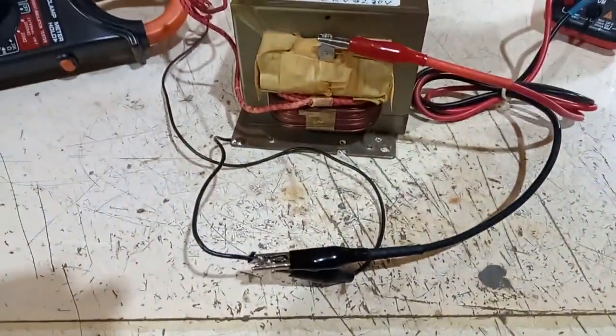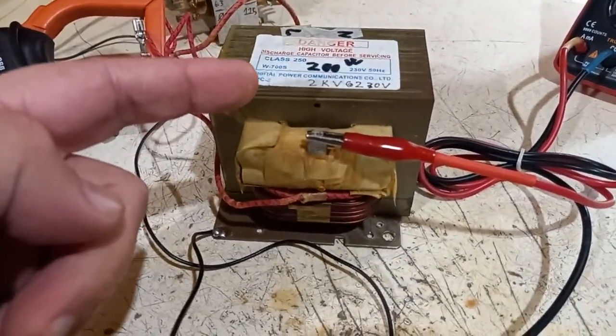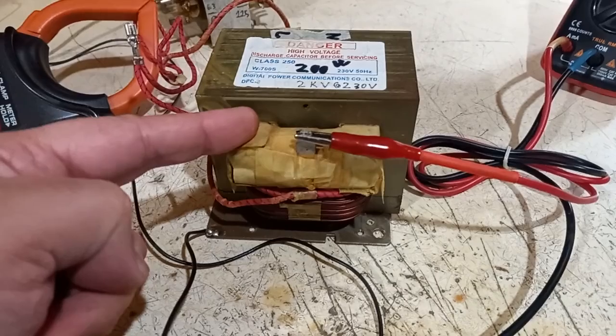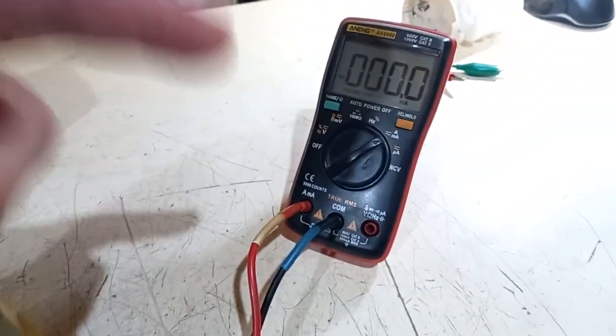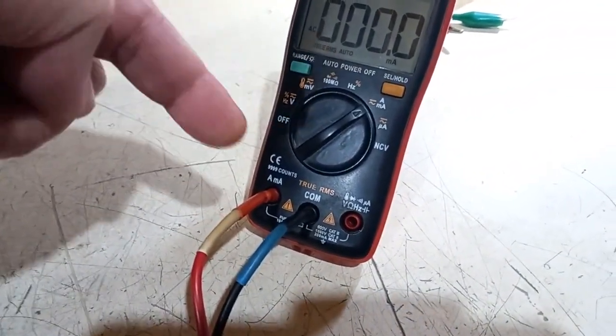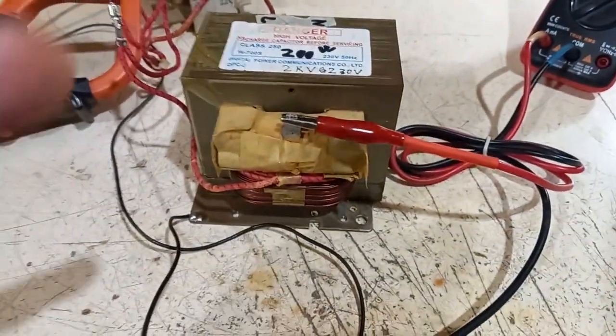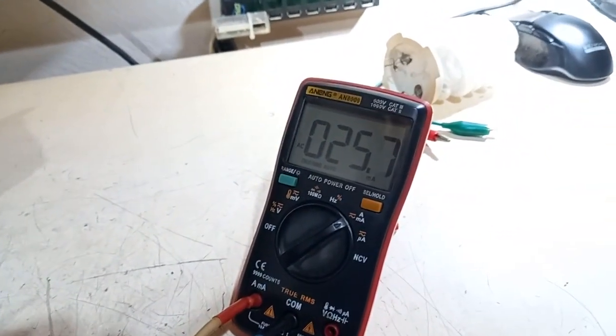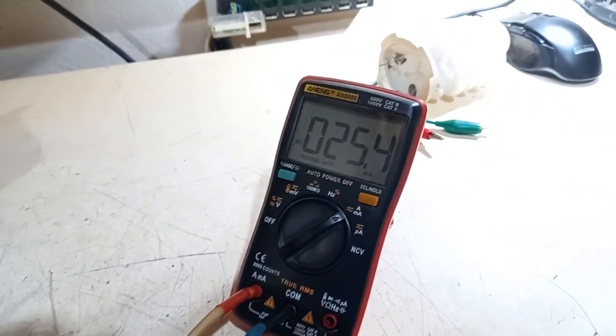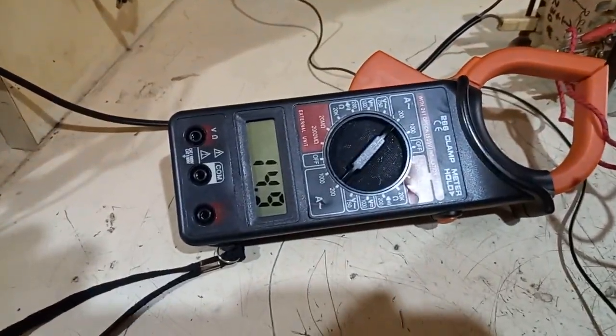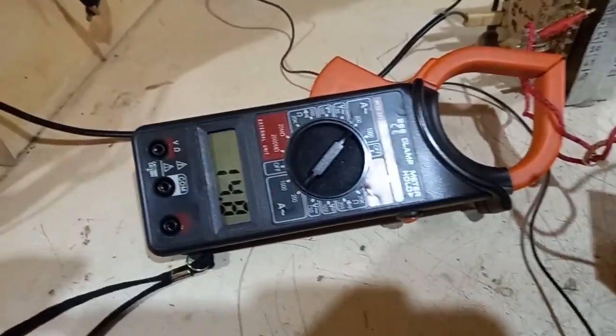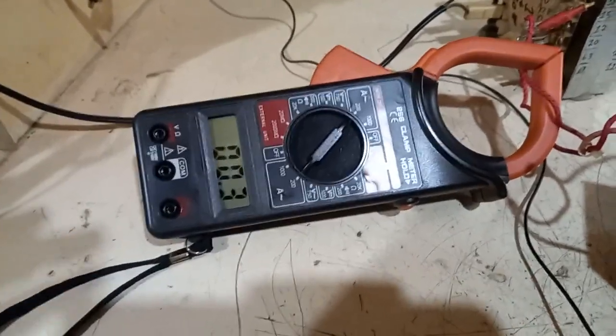Now let's read the output short circuit current of the high voltage secondary, again with the multimeter in current reading mode, with the secondary shorted. Let's turn this on - we have a current of 26 milliamperes, and a current on the primary of almost 15 amps.